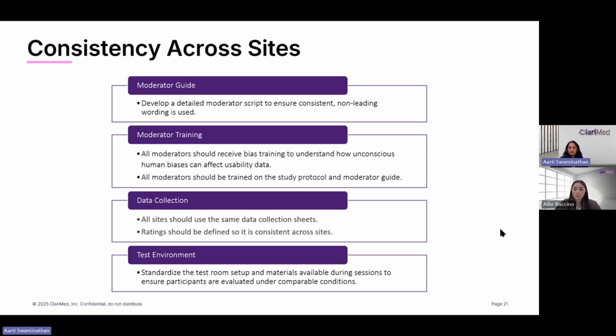Yeah, I agree. Those are all great points. And I think this also speaks to some of the points I mentioned earlier, in terms of when you are trying to conduct a human factors study at a clinical site, just making sure that you have a protocol that really lays out all of these things as scripts, as rigidly or as clearly as possible, so that you can keep that consistency across different sites and reduce the possibility of variation, because everything is really scripted out and well choreographed across all your sites.